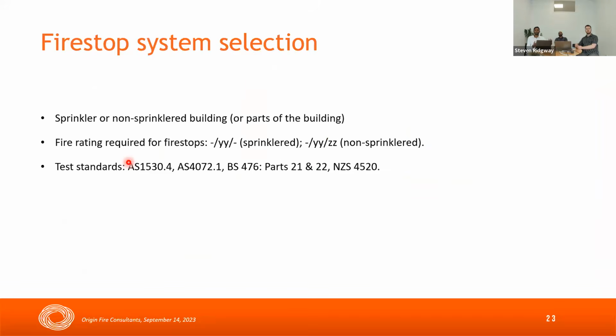The next one is the fire stop system. That's where we provide our expertise. The first thing is whether the building is sprinklered or non-sprinklered. That plays a huge role in selecting the fire stop system. If it's a sprinklered building, you don't need an insulation rating, so you only need an integrity rating for the fire stop. If it's a non-sprinklered building, then you also need the insulation rating. Sometimes different parts of the building are sprinklered. Let's say I worked on a job where only the basement was sprinklered and the apartments were not. Any fire stop installed in the basement did not need an insulation rating, but every fire stop installed in the apartments needed an insulation rating. So we make sure we understand the sprinkler requirements.